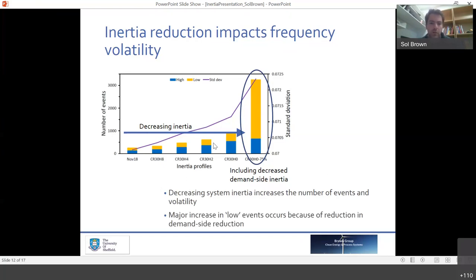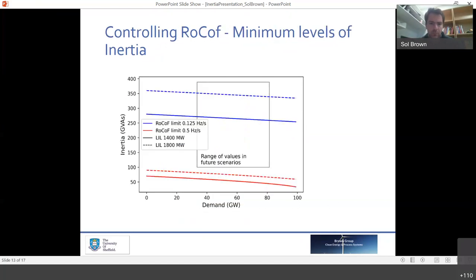But we're seeing here, importantly, a growth in the low events, where we don't have sufficient inertia and our frequency has dropped too far rather than too high. And then if we plot against that, controlling the RoCoF, the rate of change of frequency, to minimum levels as defined by the grid code, and map that against the amount of inertia on the system.